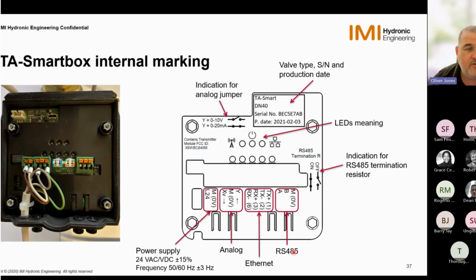And then lastly, we have the RS485 connections. So this is our Modbus and BACnet over serial 485. This is where all 3 cables are wired into. We also have, what's not shown, unfortunately, in this section here, another jumper which allows us to close the valve off wirelessly, so we can actually prevent wireless connection into the valve by changing the jumper and making the wireless connectivity within the valve dead. So if you've got certain sites where security is high and there's no wireless connections, we can ultimately switch once it's set up wirelessly, we can then turn the wireless off.